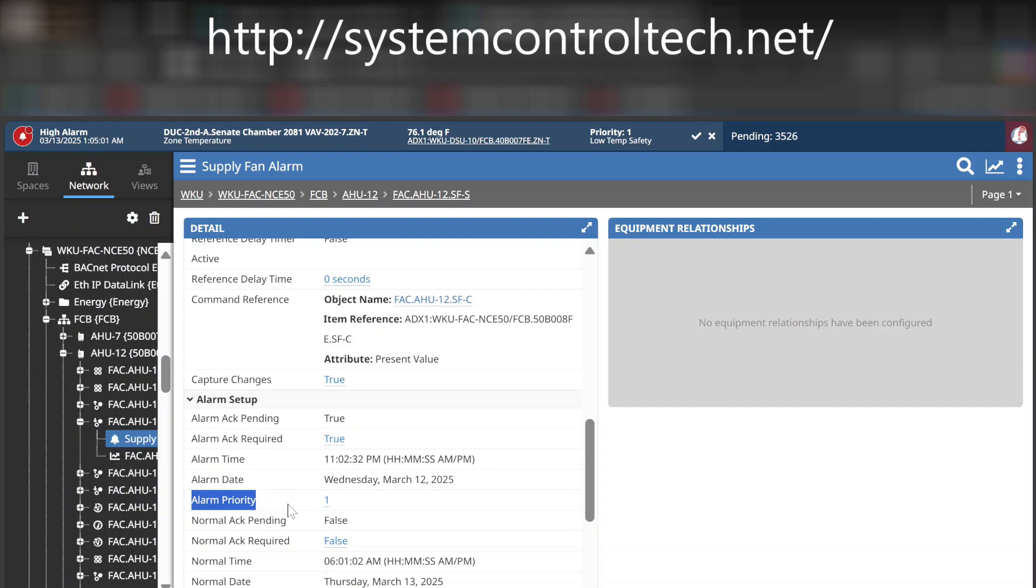As I mentioned earlier, this is how you can set those priorities to whatever you want. We currently have this to a priority level of 1, so if we get a supply fan status alarm on this particular air handler, it's going to appear at the top of our list when we sort them by priority. So by setting an alarm priority for each of the alarms, you can sort them based upon that priority, and that's one way to add a lot more of the functionality to the alarm dashboard within your system.